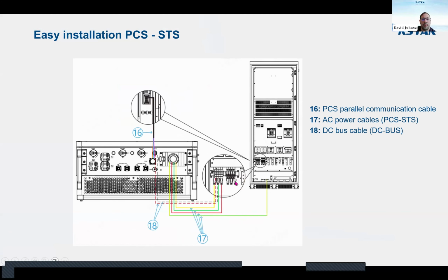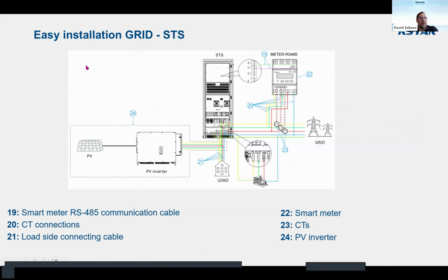Okay, regarding the inverter and the STS, the DC bus cable needs to be connected, the AC power cables, and the parallel communication cables. Regarding the connection with the grid and the STS, it has a smart meter, an RS485 communication cable that needs to be connected. The CTs need to be connected, and the load side needs to be connected. This is the customer scope, and the smart meter, the CTs, and the PV inverter also need to be set by the customer.